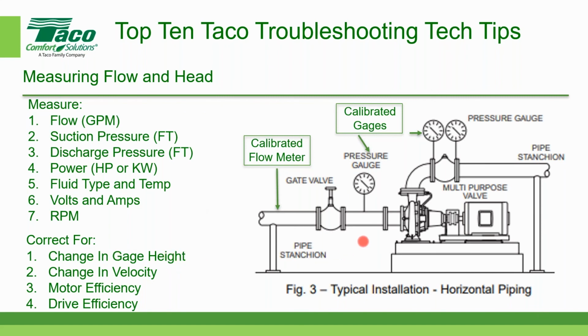So in this little example here, we're measuring the suction pressure over here, and we're measuring the discharge pressure over here, and there's an elevation change in the piping system. I ran into this not too long ago where, because of the way the gauges were physically installed and the way the piping was physically installed, there was about a 15-foot differential in elevation, but nobody told me.